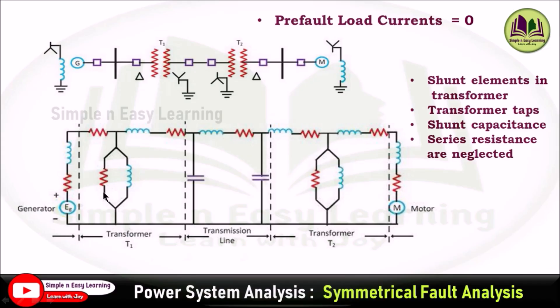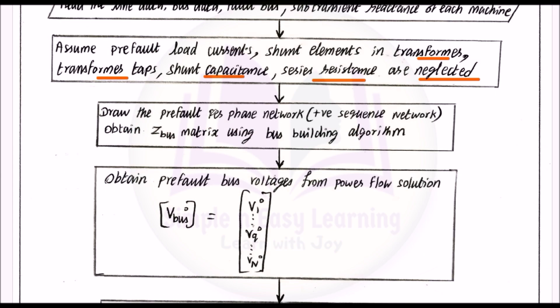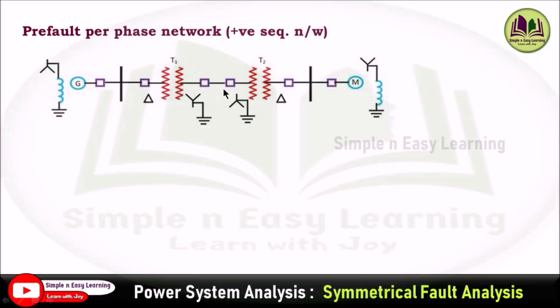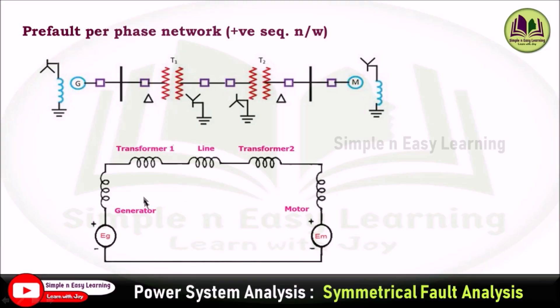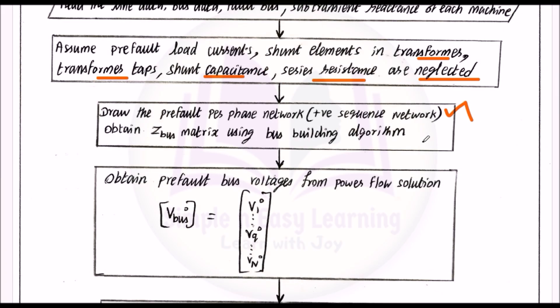In order to reduce the complexity of fault analysis, draw the pre-fault per-phase network, that is the positive sequence network. Using the positive sequence network we obtain the Z bus matrix using the bus building algorithm. For the given single line diagram, draw the reactance diagram — the positive sequence network — which consists of generator EMF and reactance, transformer reactance, line reactance, transformer 2 reactance, motor reactance, and back EMF.